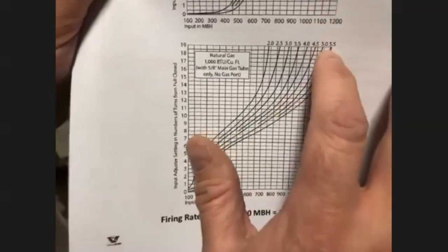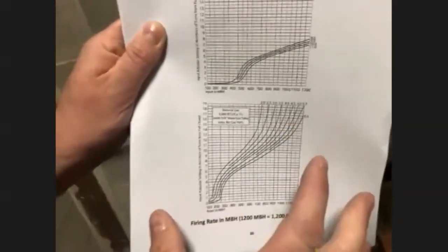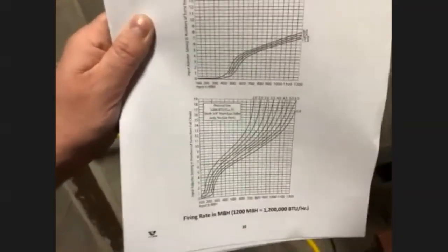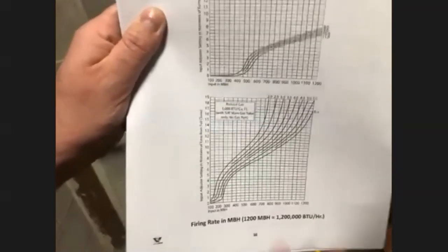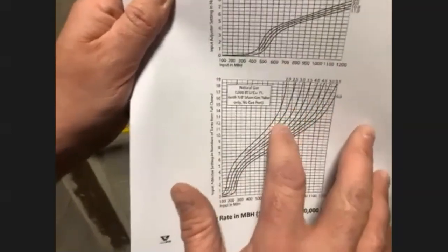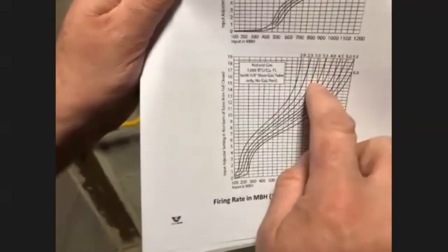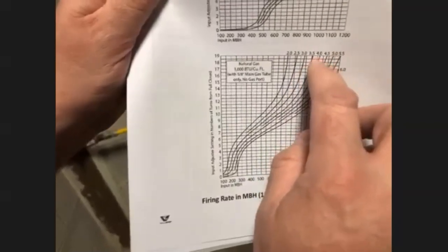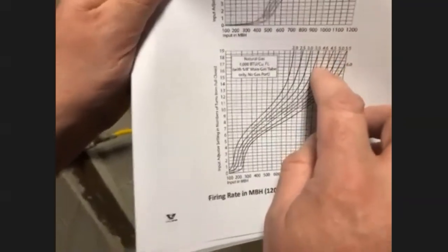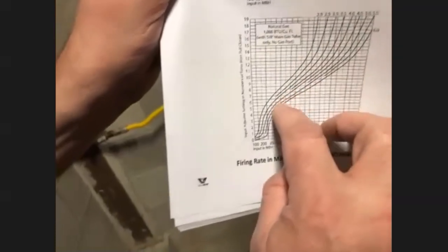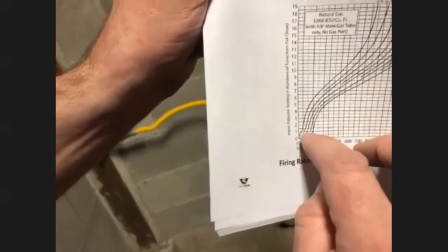And when you have the input pressure, since we're at natural, we're gonna run at 3.5 is what the setting is. And again, this is in the manual. There's other inputs in here. Your 3.5 input will come through. So we want to run down to this. Actually, I think we're at 4. I'm sorry, I said 3.5, we're at 4. So I want to follow that down. When I see that 4, it looks to be about 1.5 turns.